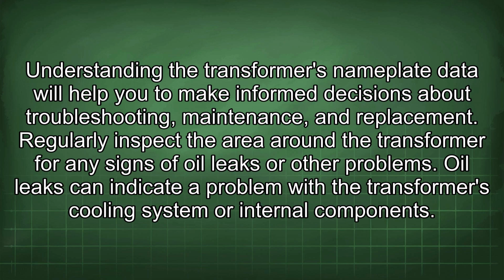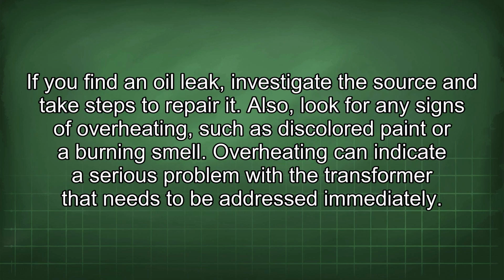Regularly inspect the area around the transformer for any signs of oil leaks or other problems. Oil leaks can indicate a problem with the transformer's cooling system or internal components. If you find an oil leak, investigate the source and take steps to repair it. Also, look for any signs of overheating, such as discolored paint or a burning smell. Overheating can indicate a serious problem with the transformer that needs to be addressed immediately.